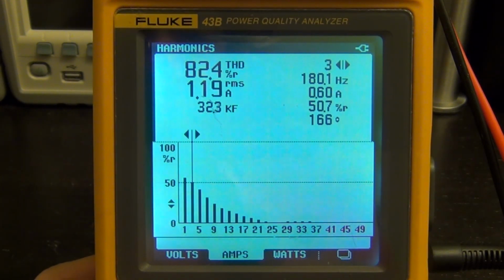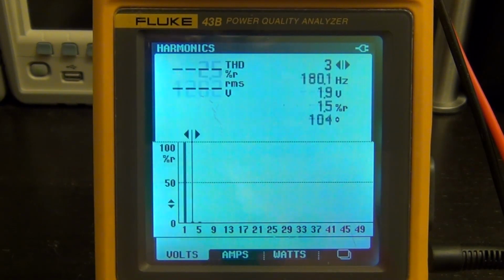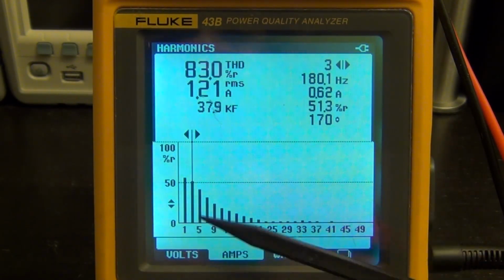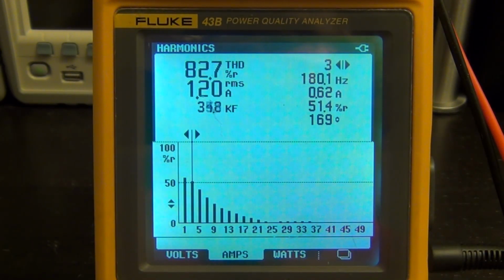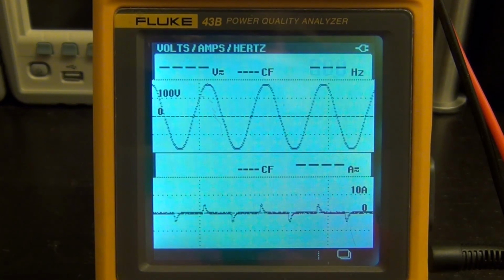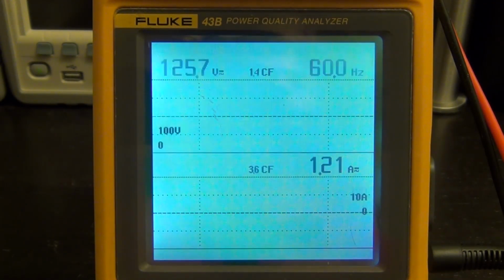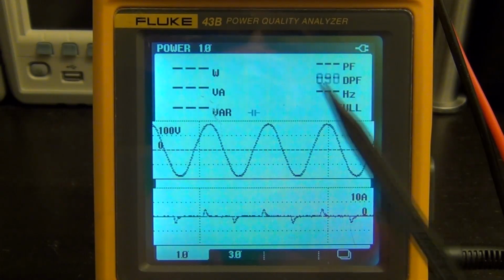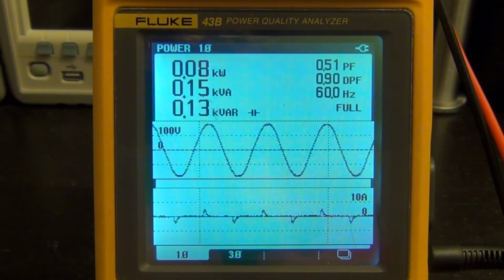And as I also mentioned, the voltage is going to look very good. The THD in the voltage is 2.5%, which is basically pretty much perfect for a voltage measurement inside the house right now. So it's pretty good. You can't really disturb that much. Nonetheless, you can see the problem with the THD, and if I continue back onto this screen, maybe go to the next one more time, that will determine the difference between the displacement power factor and the total power factor. Anyway, that's all I wanted to say.